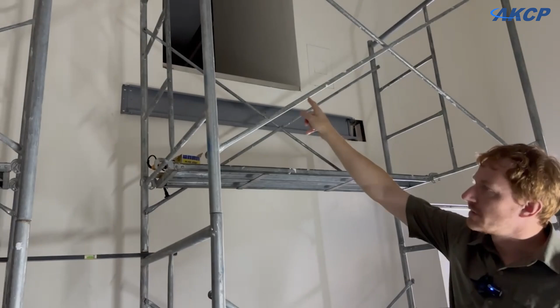We'll take a look over at the wall where these cable trays are being installed. We've got one already in up there that's going to come along and go up, continuing across to the wall above where the cable will enter and run above the ceiling into the second room. What we're bringing in this cable tray is the power running to the overhead power bars, which will supply power to our cold aisle containment facility. The hot aisle containment power bus bars will run from the wall out here and be supported on a structure standing here.